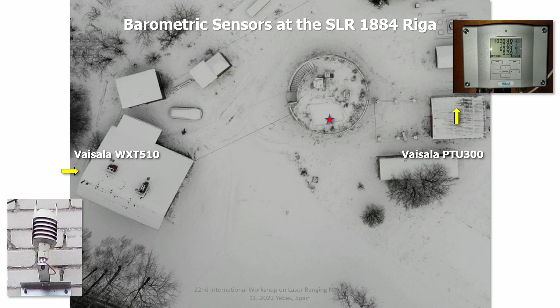The leveling was done seriously by the students - we measured where to put the device, and had the opportunity to put this reference barometer at the same height as the sensor being calibrated, to avoid any additional reduction for height differences and so on. This reference sensor was at room temperature, so it's considered stable.